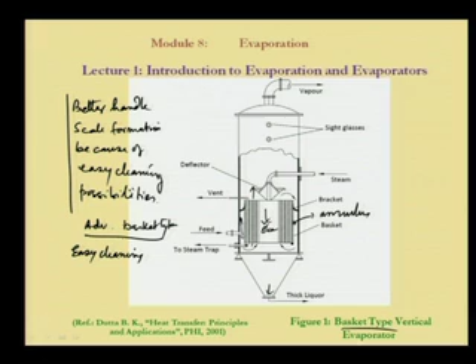Okay. So, this is the short tube vertical evaporator, that is, the basket type evaporator, which is used for natural circulation purposes. We have seen that there are three types of calandria: a normal simple calandria type, another with a propeller arrangement, and another with a basket arrangement. In the propeller arrangement, the propeller just increases the speed of circulation, which takes care of any scales being deposited, allowing them to be suspended. In the basket type, the flow direction is reversed: the steam is in the central portion and the liquid to be evaporated is in the annulus portion. The tube bundle remains like a basket, and it can be taken out easily and cleaned.